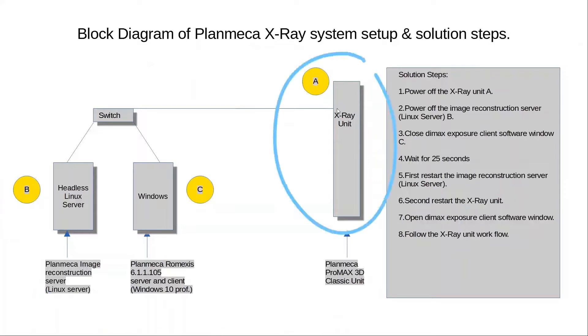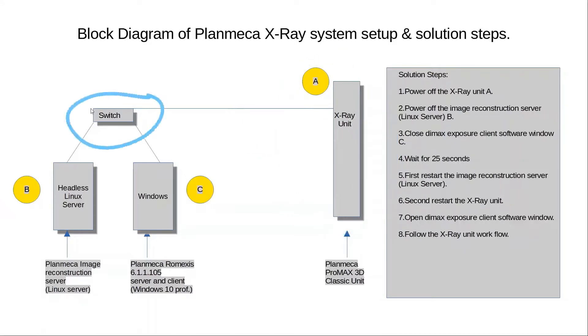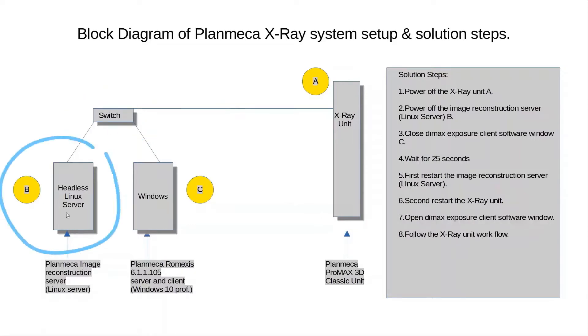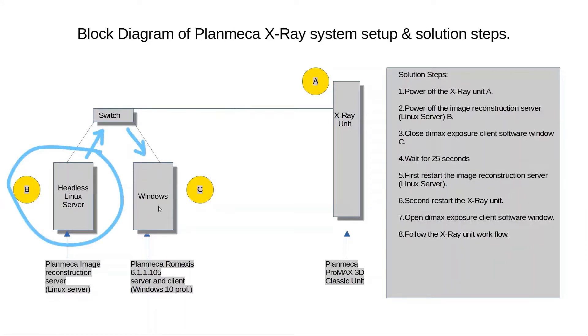The X-ray unit, represented here by A, captures the X-rays on a sensor. The captured data is sent to a switch, which passes the data to a Linux server represented by B. The Linux server then reconstructs the image from the sensor data and sends it back to the switch, which passes that information to the Windows machine.